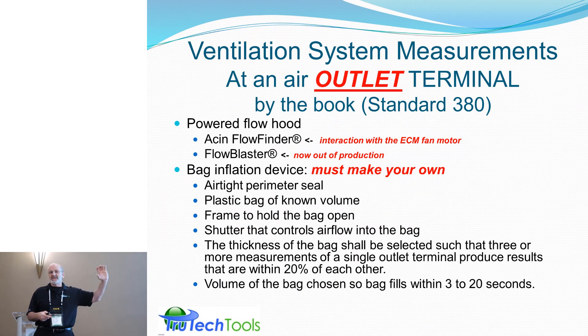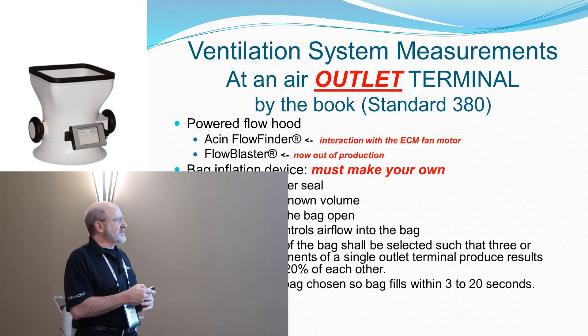We're talking about inlet, outlet measurement, and midstream measurement for this exhaust standard. At the outlet terminal, powered flow hoods are also allowed. You're all familiar with ECM motors — smart motors that react to the load in the system. The smart fan and the smart motor working together actually interact with each other. Like Alexa and Google Home talking to each other, two automated systems start talking back and forth. Because the assumptions aren't known, the fan and the powered flow hood never reach a balance point. That's been identified to the manufacturer for resolution.